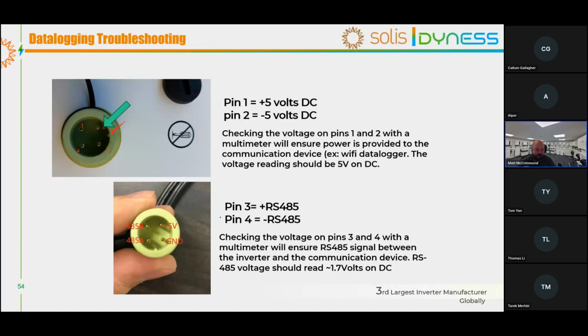If, for example, you did read voltage there, then that would indicate that there's a fault with the data logger. Then we would just RMA and send you a new data logger. If you are seeing no amber light, then it's the same situation. So we would check that your inverter is definitely producing the RS-485. So we measure pins 3 and 4, which would read values of roughly 1.7 volts. If we read that, then we're happy that the inverter's actually producing that and sending it out from the inverter. If not, we would contact our service department, explain what you've done and how it's been checked. That's just some fault finding on the data loggers.